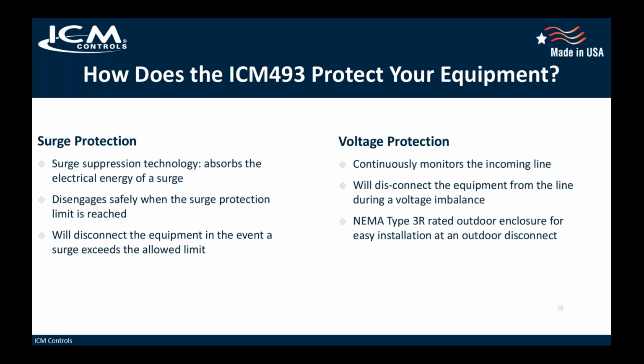So I kind of covered that, this slide, pretty much of what I just went over. You've got surge suppression technology, very much like the 517, where it absorbs the electrical energy, safely dissipating it, and disengages from the line when the limit's reached. It will disconnect the equipment and continuously monitors the incoming voltage for brownouts or overvoltage conditions. So you've got that dual benefit there. And it's in a NEMA 3R rated outdoor enclosure.